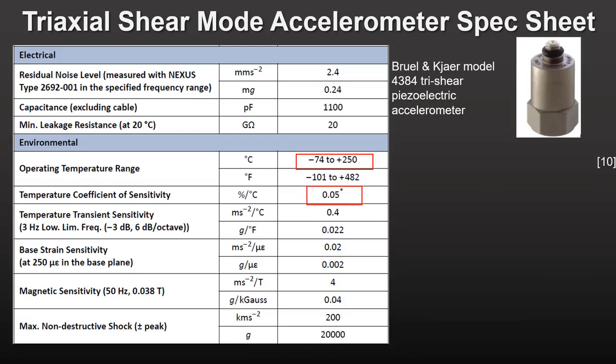The sensor operates between minus 74 and 250 degrees C, with a temperature coefficient of sensitivity of only 0.05 percent per degree C. The sensor can withstand a shock of 20,000 g's, which is an enormous number. Even with the miniaturization of accelerometers and their integration into electronic systems, piezoelectric accelerometers are still sold in high quantities, as capacitive and piezo-resistive accelerometers cannot handle such high temperatures or levels of shock and acceleration without permanent damage.